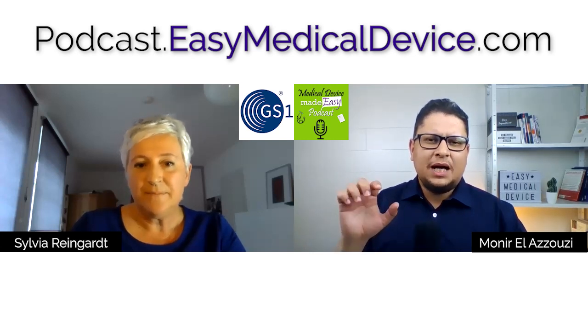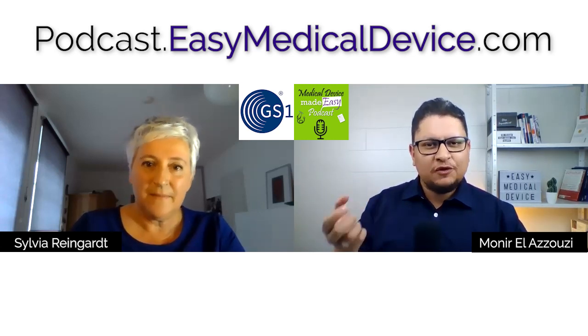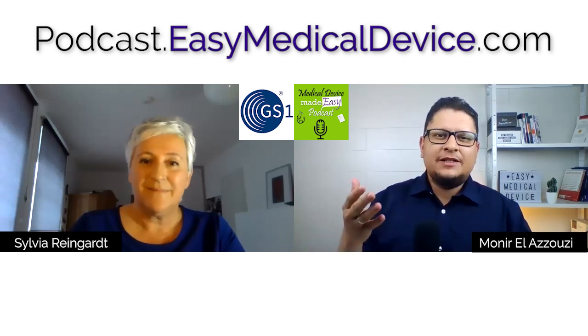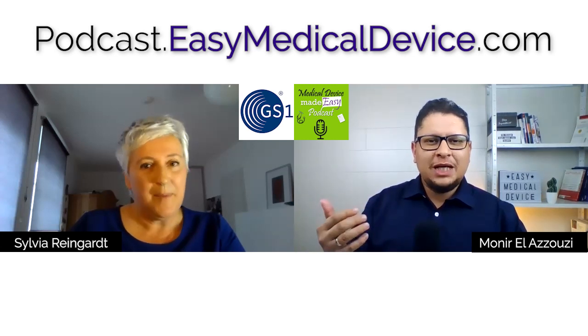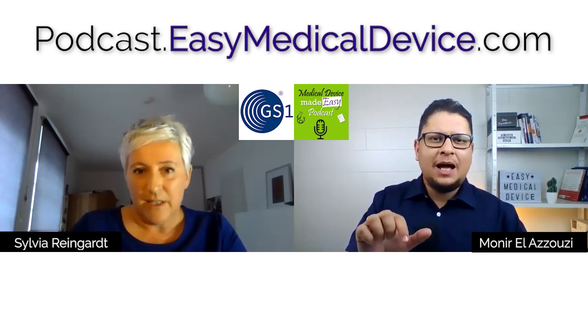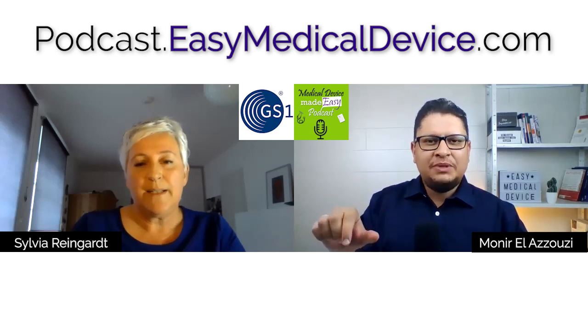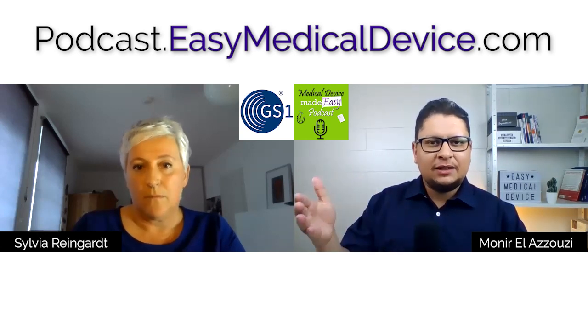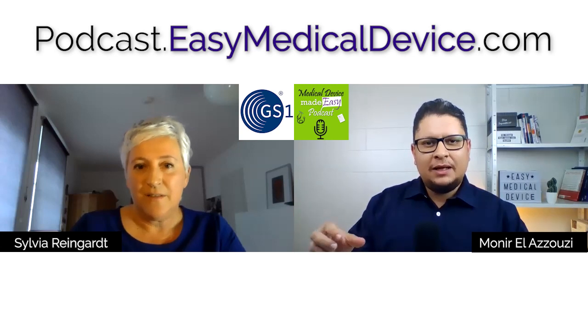The UDI-PI is mainly created by the manufacturer. It's not something where they come to GS1 and ask for a code for the UDI-PI. It's only the UDI-DI that comes from GS1, and for the UDI-PI you are just defining the standard for how you create it. There are some specifications around it. For instance, the serial number can be 20-digit alphanumeric, but not more. That's one part of our specification described there.